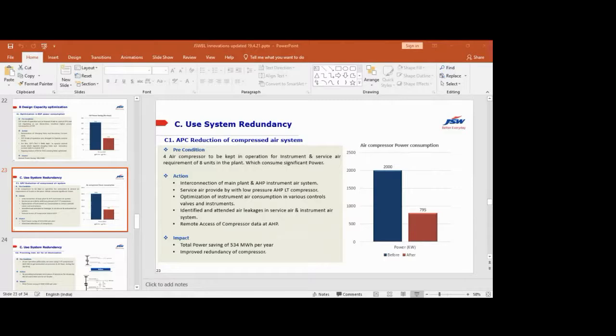Instead of 6 kg, we provided 3 kg service air, and optimized instrument air consumption in various control valves and instruments, identified and attended to air leakages, and provided remote access of compressor data at the ash handling plant so that we can monitor the loading and unloading of the compressor. By doing this, we are operating only 1 compressor right now, and the other 7 compressors are on standby. So we are saving the APC as well as the maintenance cost of this equipment.